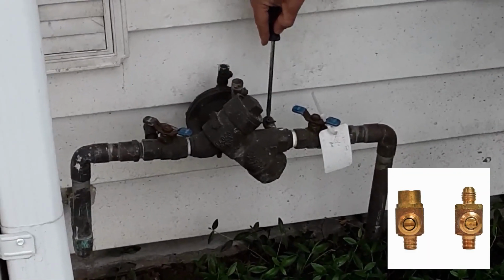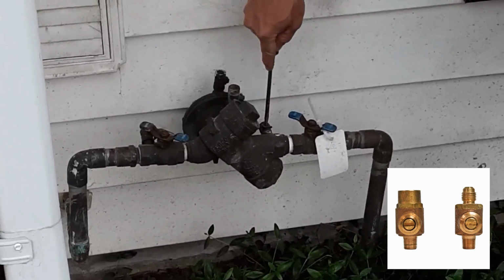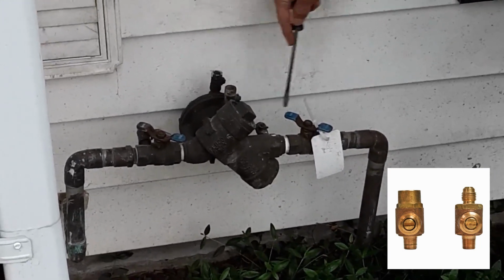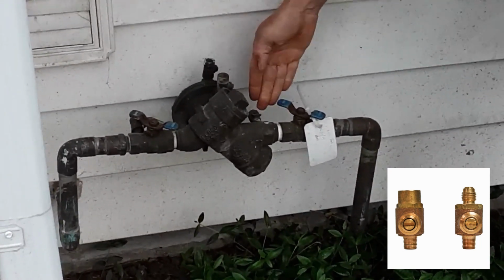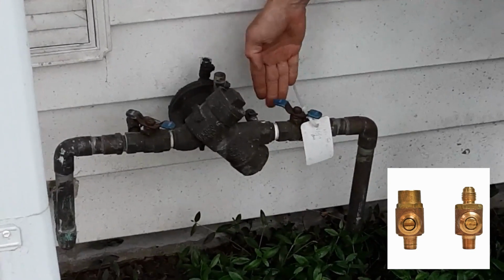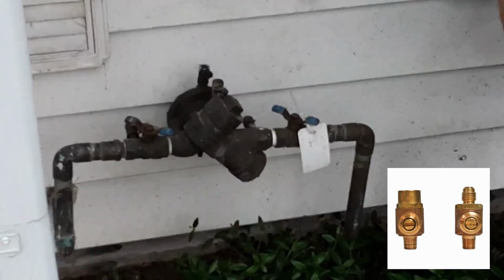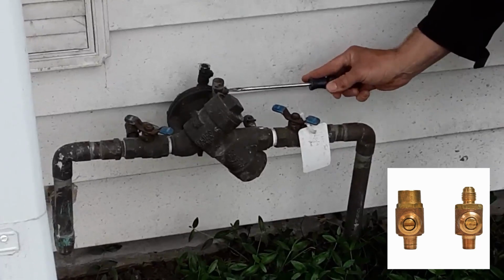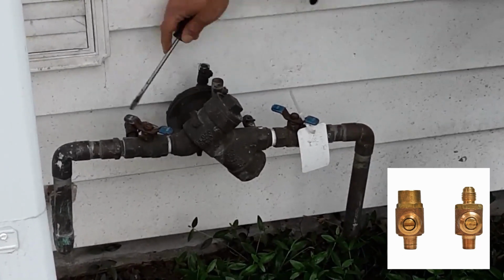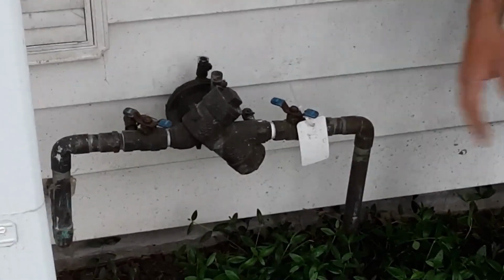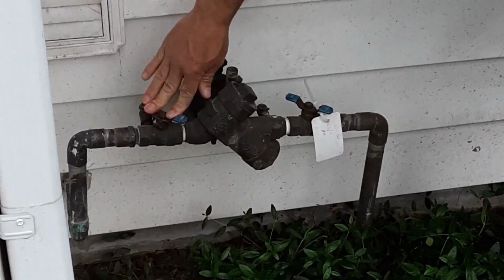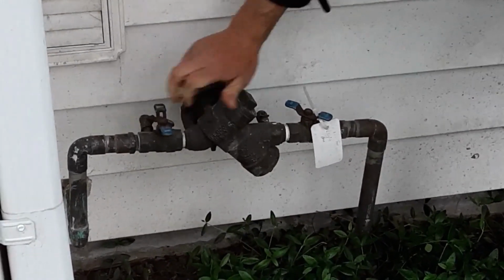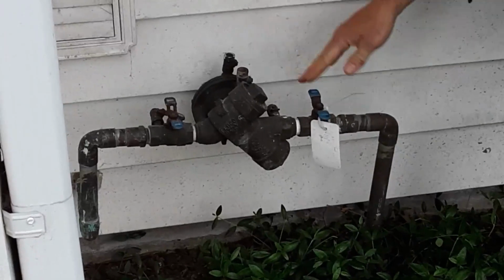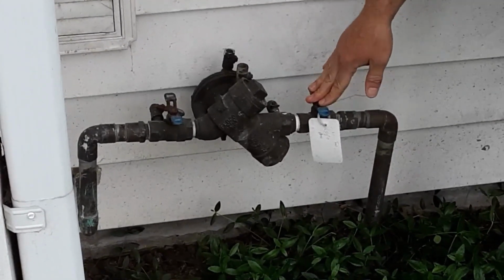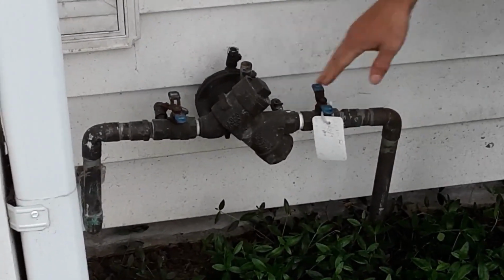In order to close those, use a screwdriver and just turn the slot in the screw head to be perpendicular to the pipe. So the pipe goes this way. You want to turn that screw head so that it is perpendicular to that pipe. So we'll do that for all 4 of these. And then this one here as well. And there are these 2 main shutoffs. I'm going to close these for this stage of the operation, and then we'll come back to these in a few minutes after we turn the water on inside and reopen these.